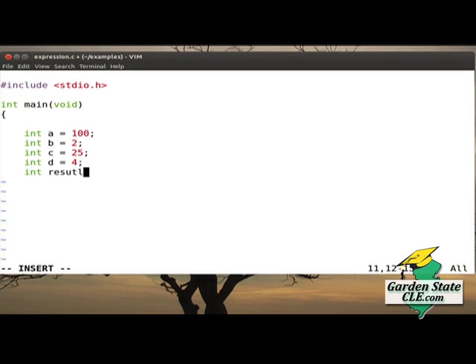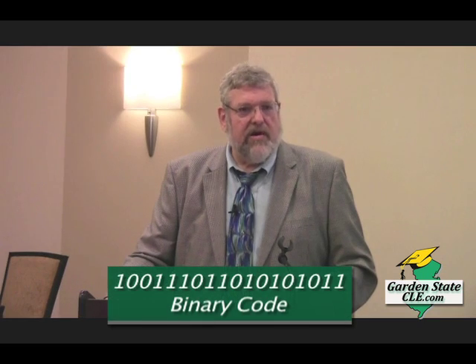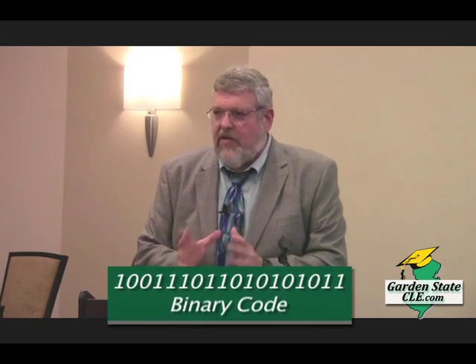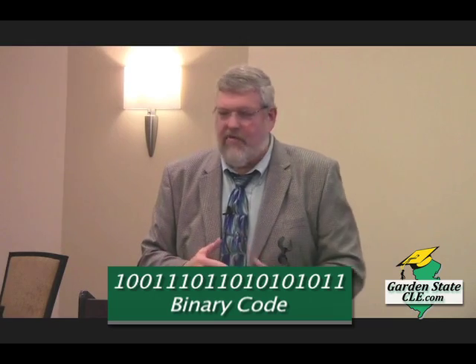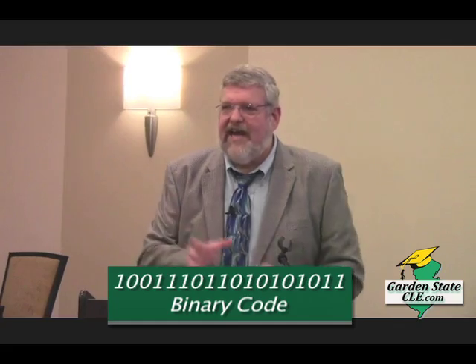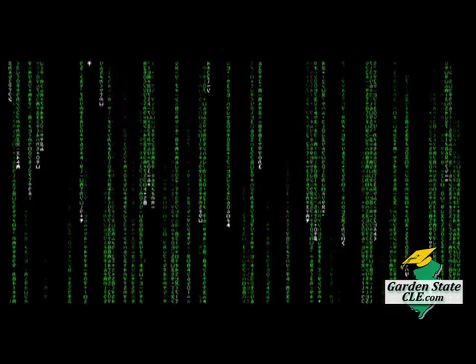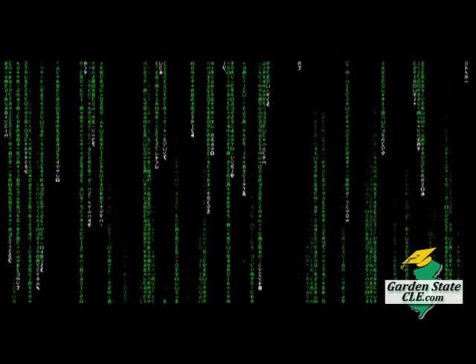That code is human recognizable language. That's what we do software in, human recognizable language. It's programmed in a language called C. That then runs through a computer program called a compiler. And it turns it, for want of a better way to explain it, into the ones and zeros that a computer can read. Once it gets compiled into the ones and zeros so the computer can read it in here, you can't tell which 1 and 0 has to do with the guy's weight, his age, whether the control test number is right, whether the readings were calculated properly for the Alcotest.